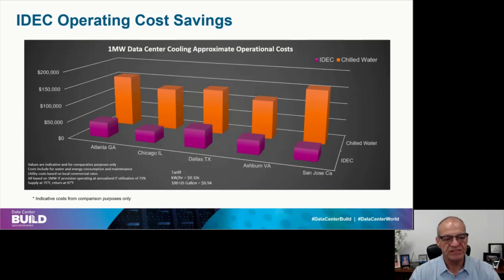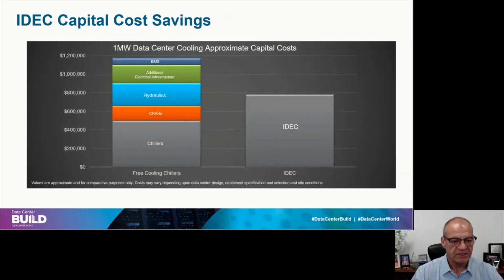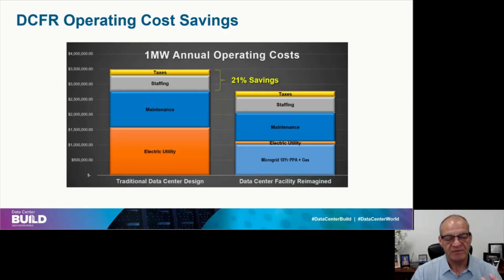Across the cities, it's a fraction of the operation of a chilled water solution. From a capital cost standpoint, once you consider everything, a free cooling chiller system versus an IDEC comes out at less than 70% of the cost of that system. Operating cost savings are about 21%, and that includes, if you look at the blue area, the microgrid, the cost of the PPA and the gas. You can see there's still a little bit of electric.